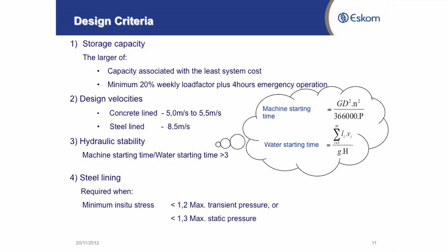If you design a pump storage scheme, the first thing you look at is what size of dams do I require? What we followed in Drakensberg was quite easy. It was decided we use a 28-hour dam, and together with the additional pumping we have to do with water phase, it came out to a certain volume that we required. Here was a different story. We said, okay, we already have two pump storage schemes with large storage capacities. We probably don't need this anymore. This is huge storage. So let's look at the total system cost. By changing the various dam sizes and doing this total system cost, we found out what the most optimum size was. That is the way we did that.